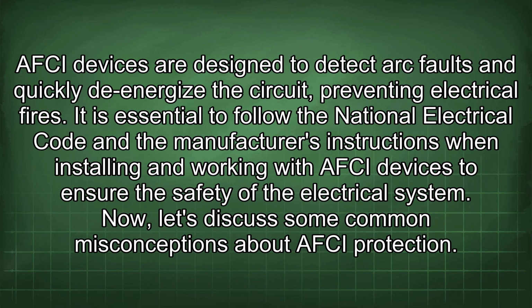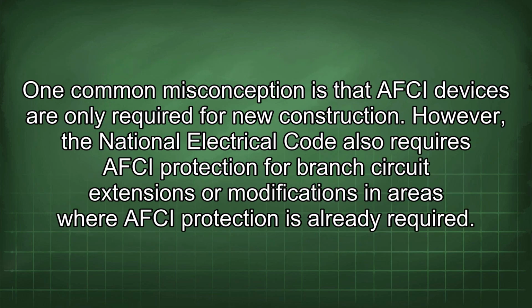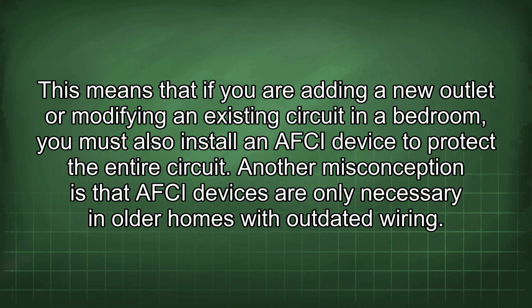Now let's discuss some common misconceptions about AFCI protection. One common misconception is that AFCI devices are only required for new construction. However, the National Electrical Code also requires AFCI protection for branch circuit extensions or modifications in areas where AFCI protection is already required. This means that if you are adding a new outlet or modifying an existing circuit in a bedroom, you must also install an AFCI device to protect the entire circuit.